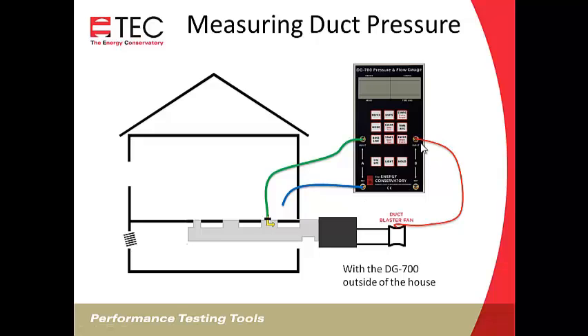And with the B channel, what we're measuring is the fan pressure, the pressure at the flow sensor of the Duct Blaster fan, with reference to the space that flow sensor is in. That's what we need to do with the DG700. If we're in the same space as that flow sensor, we don't need a tube connected to that. But if we're depressurizing and we turn that fan around, now our flow sensor is on the inlet side of the fan with the rings on, inside the flex duct, and we need to run a tube from the reference to the T connection on that round transition piece.